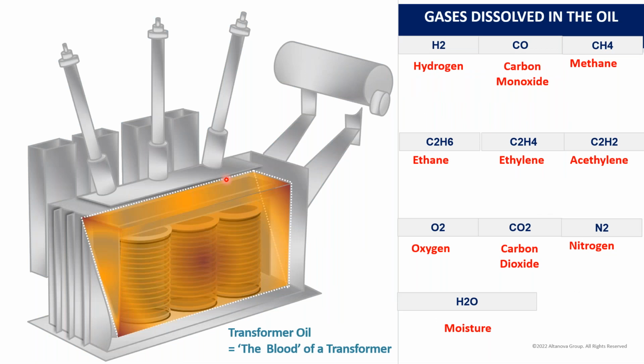DGA means dissolved gas analysis, because when you have a higher temperature in the transformer or partial discharge in the transformer, it will produce gases. The first one produced will be hydrogen. Then you will have methane. Then you will have, let's say, carbon monoxide, ethane, ethylene, acetylene, oxygen, carbon dioxide, nitrogen. These are the most important and basically standardized gases. When I say standardized, there are numbers related to how much of these gases can be in the oil of the transformer.